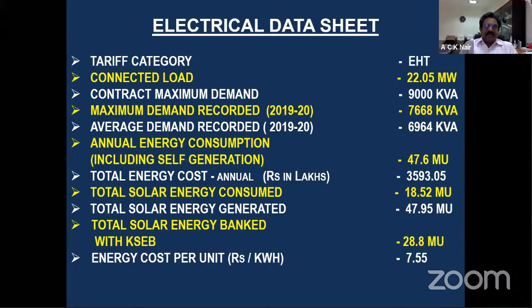We have a 110 kV substation as our main power feeding substation to the airport. Connected load is 22.05 megawatt, maximum demand recorded is 7,668 kVA, average demand is 6,964 kVA, and annual energy consumption is around 47.6 million units, with total energy cost at 35.93 crores per year.